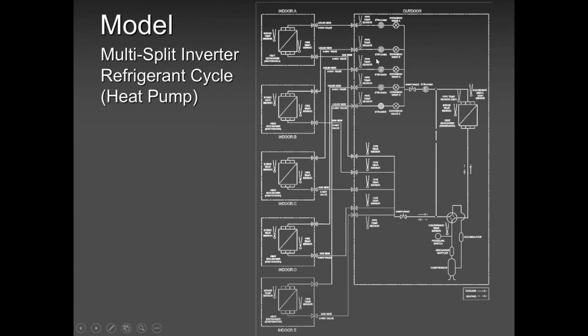So in this case, we have a 5 zone. So we have 1, 2, 3, 4, 5. We have 5 indoor units that are connected. Our biggest problem, guys, please remember, when you're doing your piping, do not cross. Do not cross your pipes. Do not cross your wires. It will come to bite you big time, especially in the summertime, not in the wintertime, because in winter you're running it in heating, and heating does not have an error code for crossing of wires or crossing of piping. Okay, so please keep that in mind.